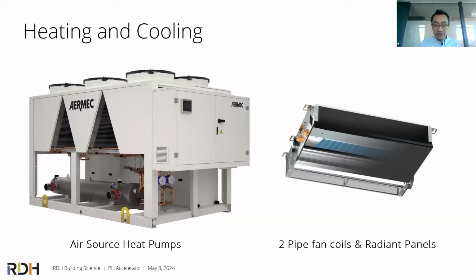Fan coil units allow for a faster response time to temperature fluctuations within a space. And radiant ceiling panels allow for the ability to centralize maintenance, as the panels don't require the same regular maintenance as the fan coil units. There's no filter, there's no fan. And so radiant panels are really great for spaces like the Great Hall, multi-purpose rooms, and youth lounges.